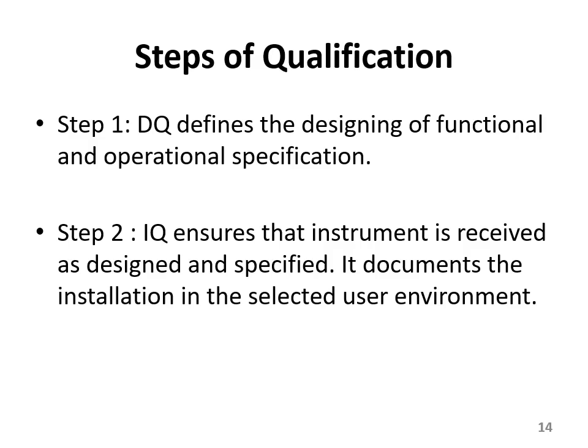Step 2, installation qualification, IQ, ensures that the balance or instrument is received as designed and specified, right? So in installation qualification, as a second step after design qualification, you need to know how the process or the product was designed, and when you are receiving it, is it in the same condition it was designed, or it was asked to design and it was asked to specify.